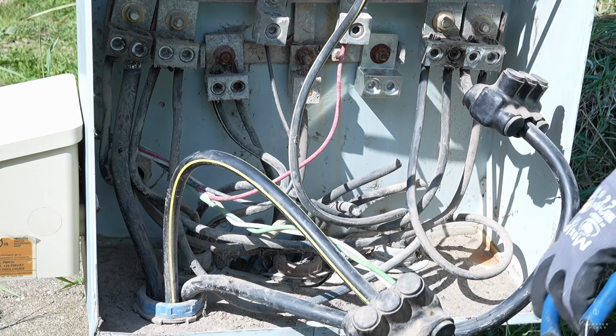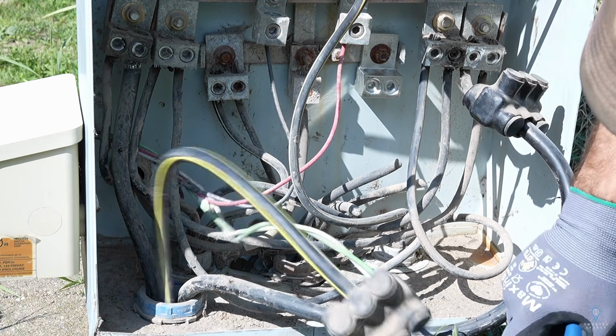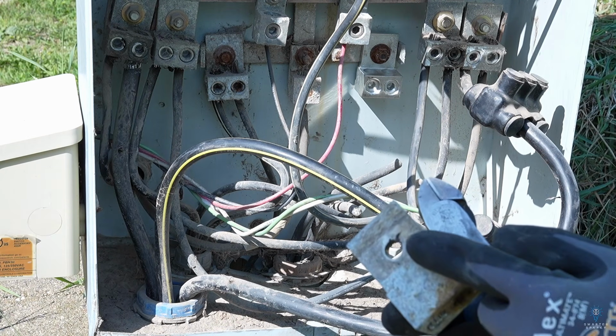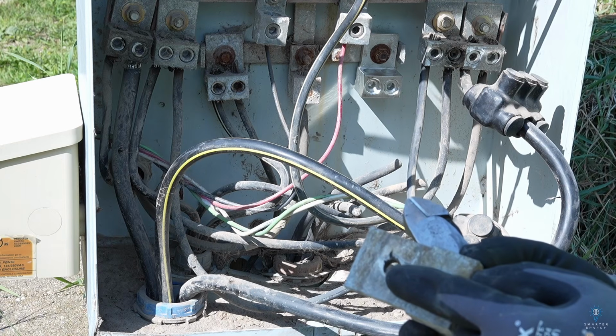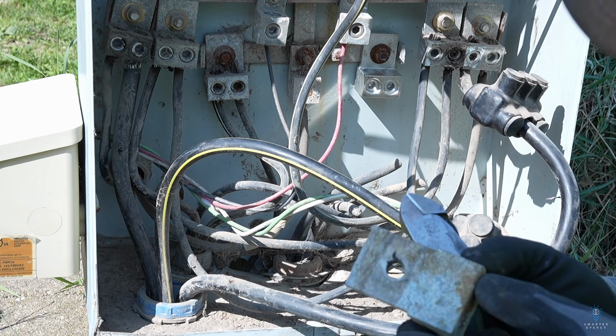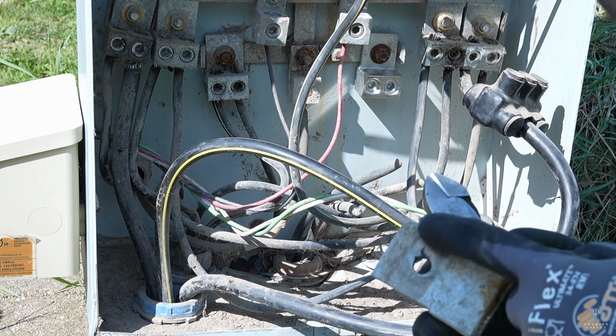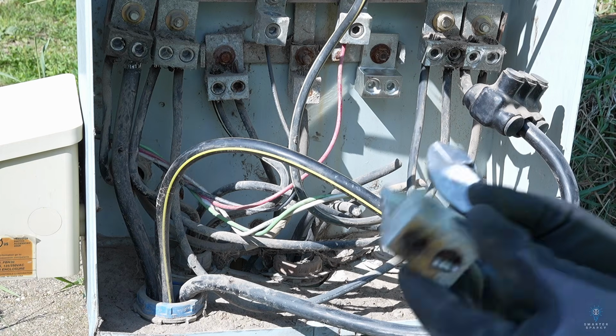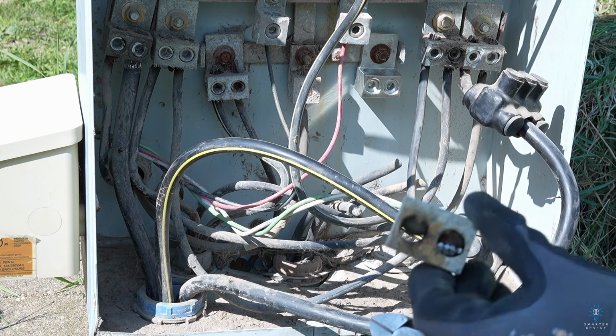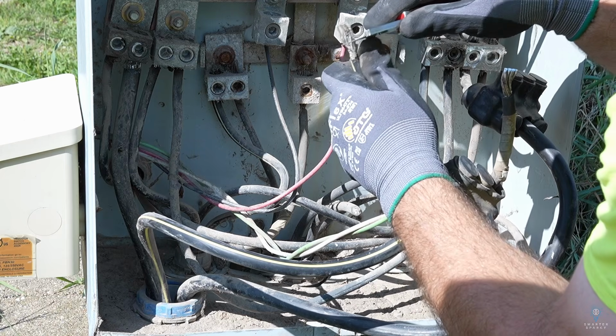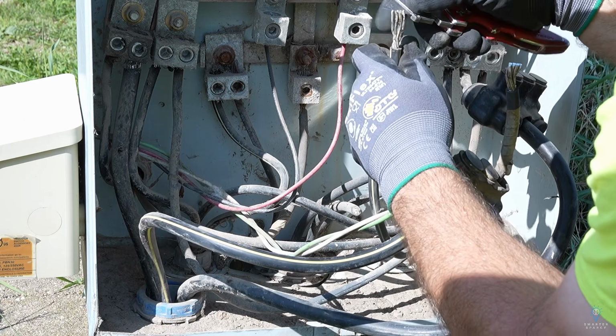So I'm just gonna cut this off here. I'm guessing that corrosion was starting to creep into the back side here. I mean, you can still see there's a little bit of shininess back here, but that corrosion's getting so bad. I'm guessing right here is where our voltage drop came from. I mean, we'll find out here in just a minute. And these conductors, yeah, they look just fine.